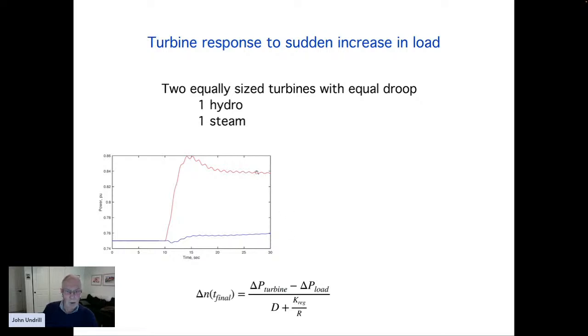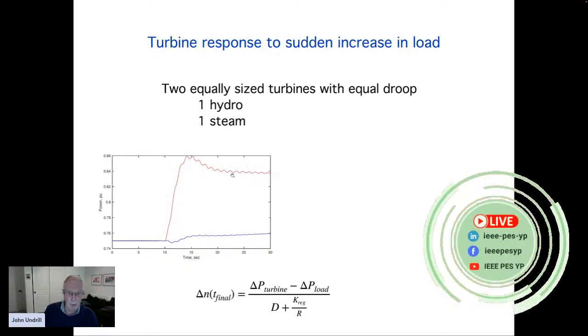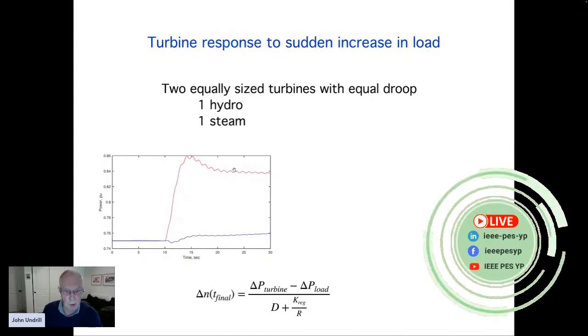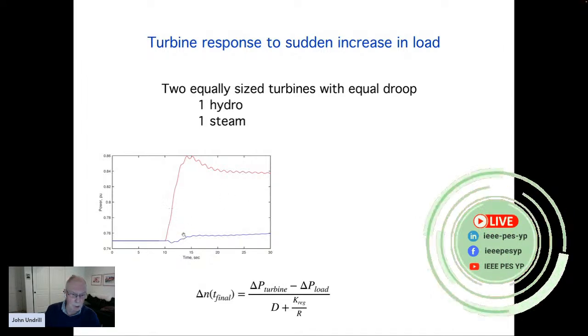Let's assume that we've got two equally sized turbines, let's say 200 megawatt turbines. They're both operating with an equal droop, so that slope of that drooping line is 5%. One of them's a hydro unit and one of them's a steam unit. Same size, same droop, same load. So here they are operating each at 75 megawatts. And somebody turns on a large block of load. Somebody starts a large chipper motor in a paper mill. Somebody starts a large compressor in an LNG facility. A rolling mill starts up in a steel mill. But there's a sudden increase in load. The load goes from 150 to 160 megawatts, but each generator would be expected to produce half of that change.